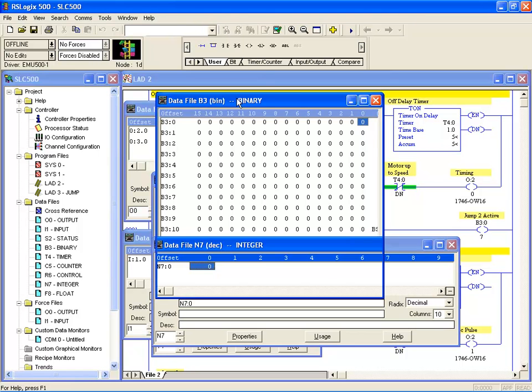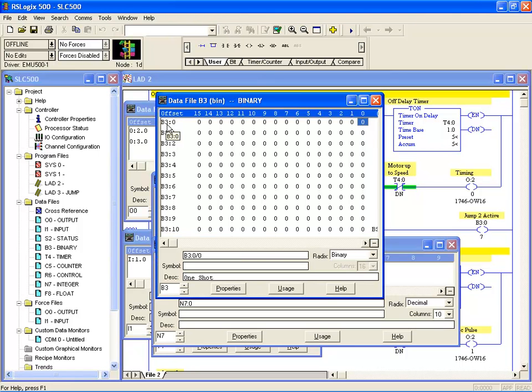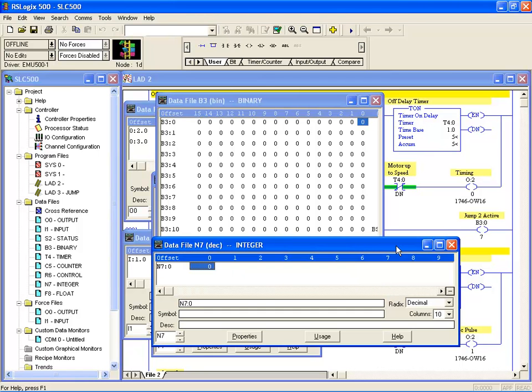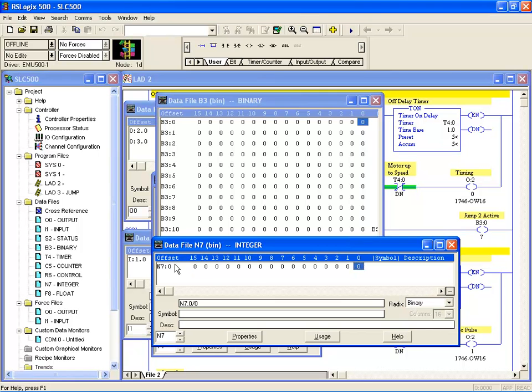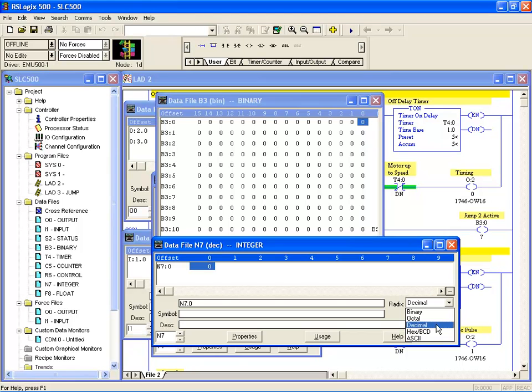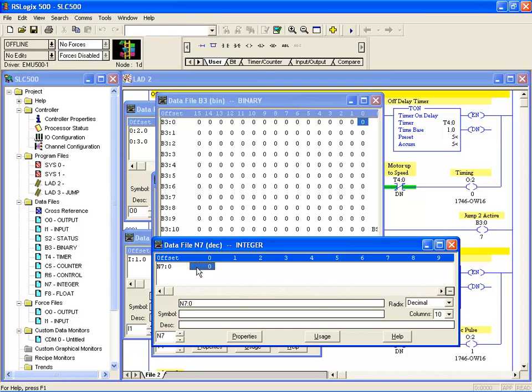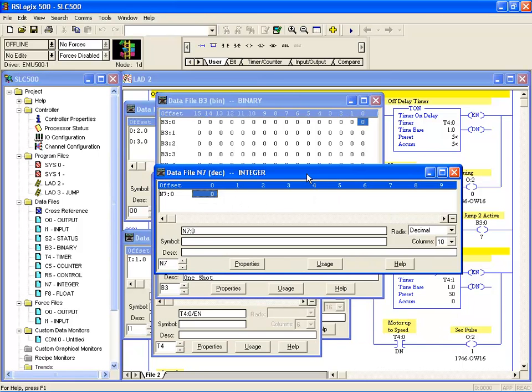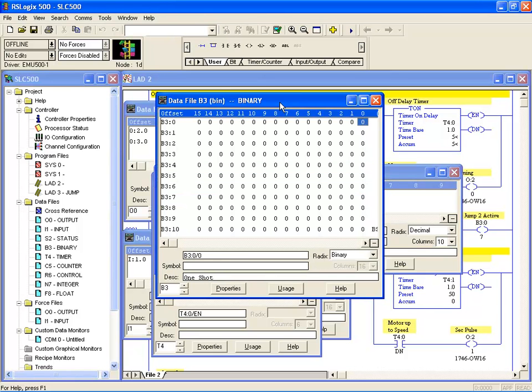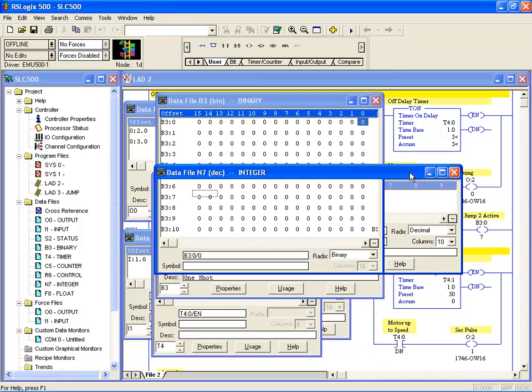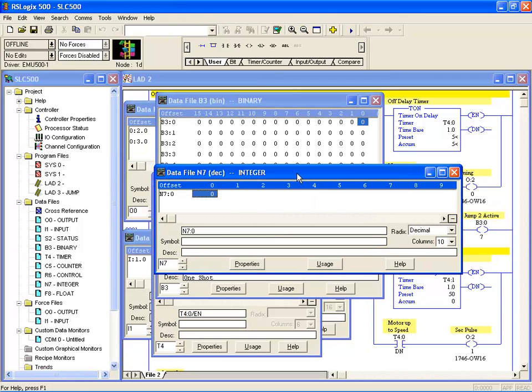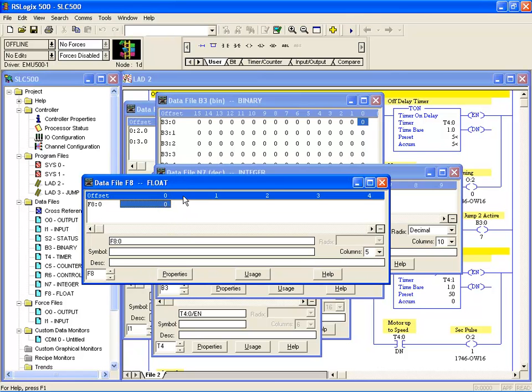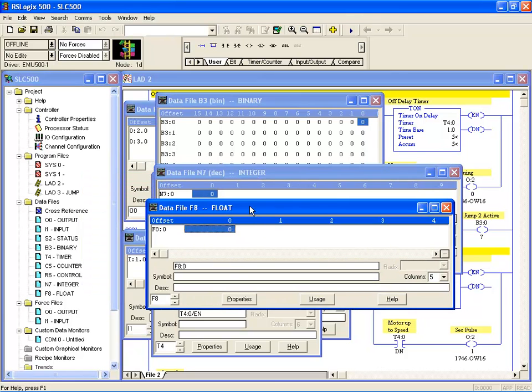When you're addressing an integer file, it's referred to generally as N7 0 and so on. Whereas when you're referring to a binary file, you refer and address to bit level more commonly. Although I can change the display here from decimal to binary to show the integer file in its bit format, the most common and widely used way is to show it in decimal because that's where we'll hold values. Certainly in future lessons we'll be using those integer files to manipulate and store our data. When we're referring to the memory map, we can think of integer words as being 16 bit words and binary words as being a bit.